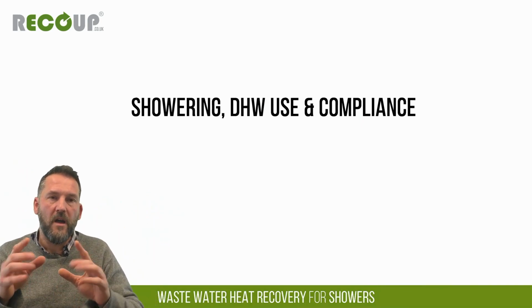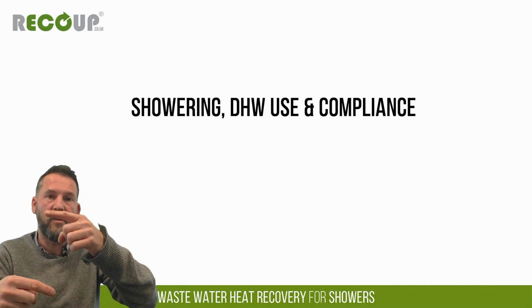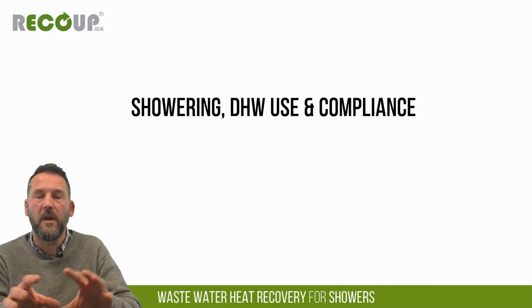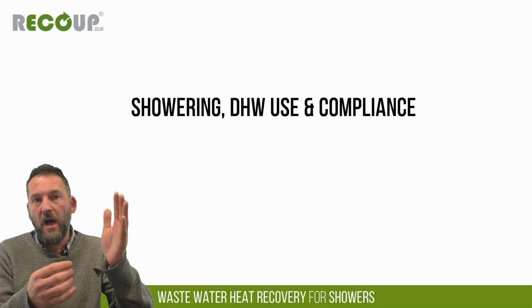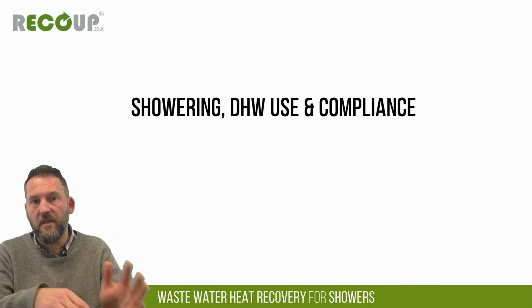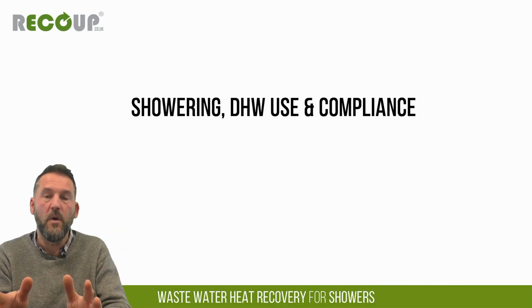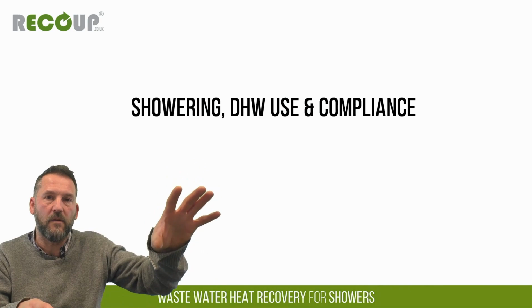So we rely on that warm waste going down because that's our only heat source, and cold water main coming in to be preheated. So whilst technically you could feed it to other areas and it wouldn't be SAP compliant that way, it could be done, but you wouldn't get any benefit. So for instance, with a shower over bath, you're only getting a benefit of wastewater heat recovery when the shower's running. When the bath is filled up and you sit in the bath and it goes a bit cooler, and then you pull the plug, there's nowhere for that heat energy to go unless you just happen to be refilling the hot water tank or something at the time.